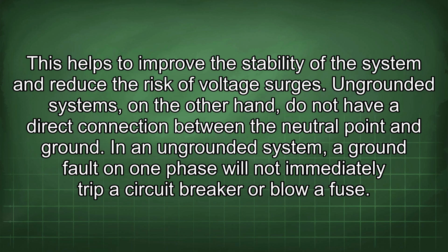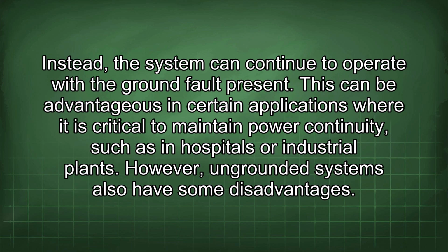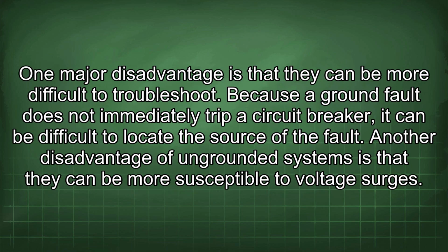Ungrounded systems, on the other hand, do not have a direct connection between the neutral point and ground. In an ungrounded system, a ground fault on one phase will not immediately trip a circuit breaker or blow a fuse. Instead, the system can continue to operate with the ground fault present. This can be advantageous in certain applications where it is critical to maintain power continuity, such as in hospitals or industrial plants. However, ungrounded systems also have some disadvantages. One major disadvantage is that they can be more difficult to troubleshoot. Because a ground fault does not immediately trip a circuit breaker, it can be difficult to locate the source of the fault.